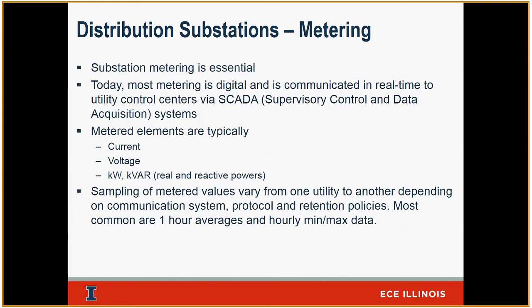At Ameren, we use what we call a SCADA system, supervisory control and data acquisition system. Here I have a meter, and next to the meter I have a radio. This radio could be a basic 900 megahertz radio, a cell modem radio, or a microwave radio. Different technologies can be used to communicate these measured quantities. I measure those through a meter, and then communicate them through a radio back to a central location. That central location collects all that information from every substation and every meter, and stores it in large databases so our engineers can analyze and study it.